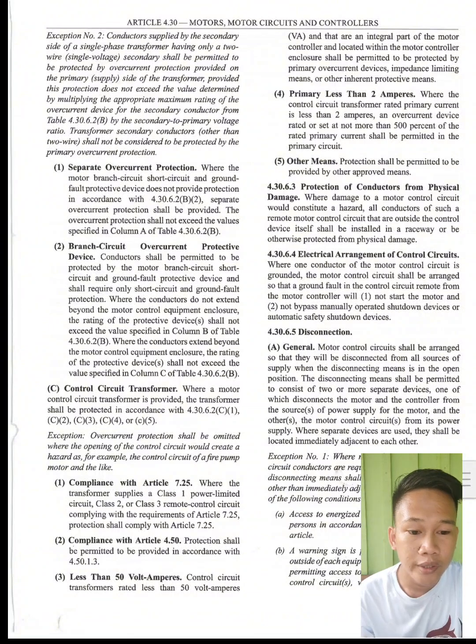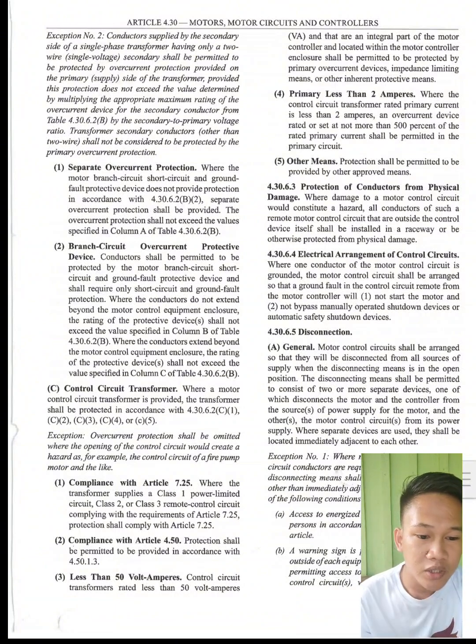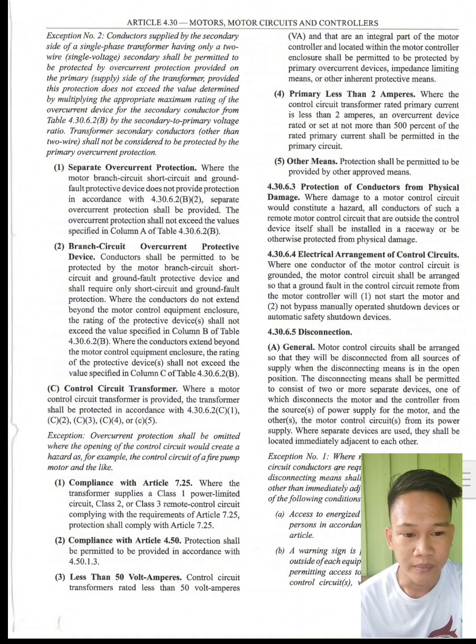So next, we have 4.30.6.5 disconnection. In general, motor control circuits shall be arranged so that they will be disconnected from all sources of supply when the disconnecting means is in the open position. The disconnecting means shall be permitted to consist of two or more separate devices, one of which disconnects the motor and the controller from the sources of power supply for the motor, and the others, the motor control circuit from its power supply. Where separate devices are used, they shall be located immediately adjacent to each other.